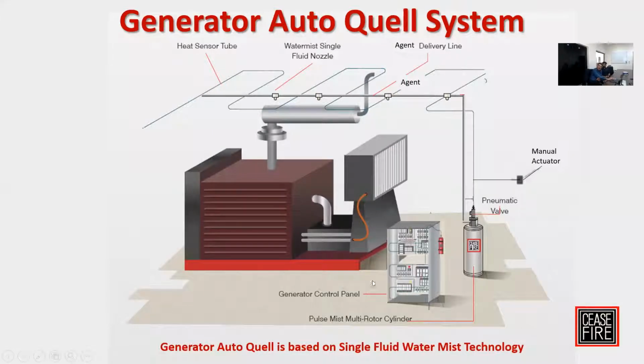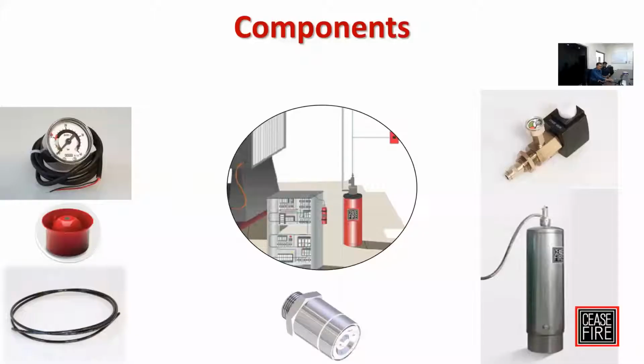There are generators which also have control panels. To protect these control panels, we don't recommend going for the water mist technology. We protect these panels using our tube-based, gas-based suppression system. So a complete offering from our end is water mist protection for the generator canopy, and for the electrical cabinet, you need to protect it with a gas-based, tube-based system. The entire system is automatic. In case of fire, it will be actuated automatically and quench the fire rapidly, immediately. So that is the schematic of the system.